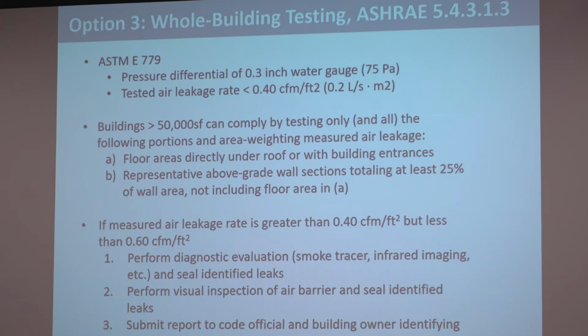ASHRAE has the similar whole building air testing requirements, same air leakage rate requirement, 0.4 CFM per square foot. They go into additional detail about building size. Bigger buildings don't have to do a whole building air test, which is incredibly complicated to do. They can just test the specific areas of the building. So if you've got a high rise, you've got to test the top floor, you've got to test the building entrance floor, and then about 25% of the other floors. So you can get a representative area.